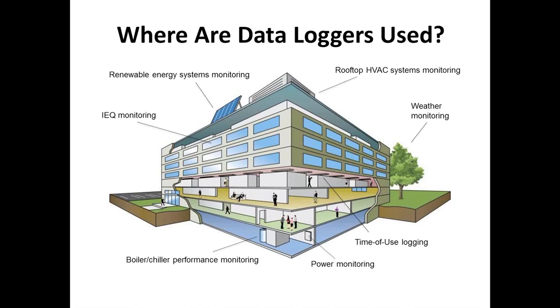We can put time of use logging in. It actually records event changes, whether a light fixture was on or off, and lets us figure out what the actual schedule of the lighting is, so we can make improvements. And we can install motor on-off data loggers to tell us when a motor was turned on versus when it was off.